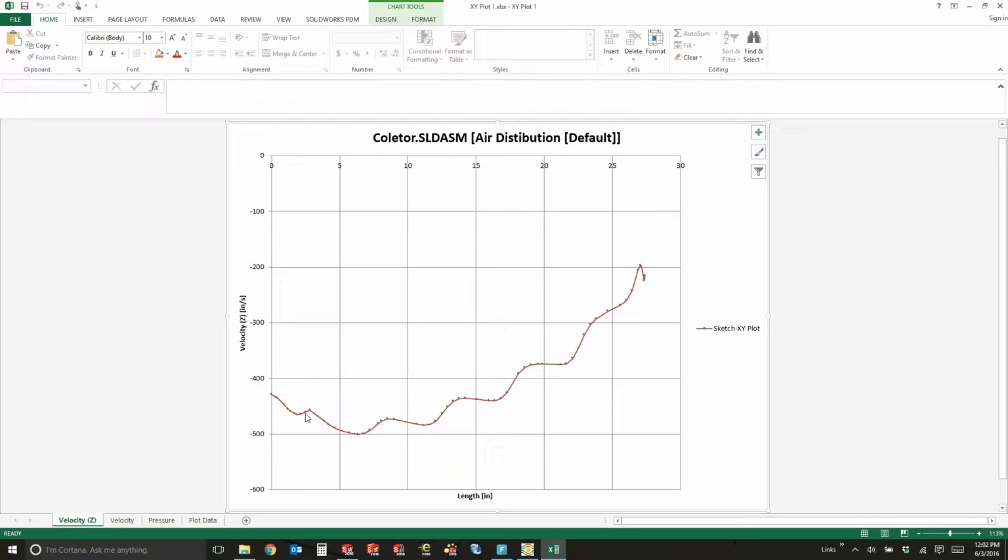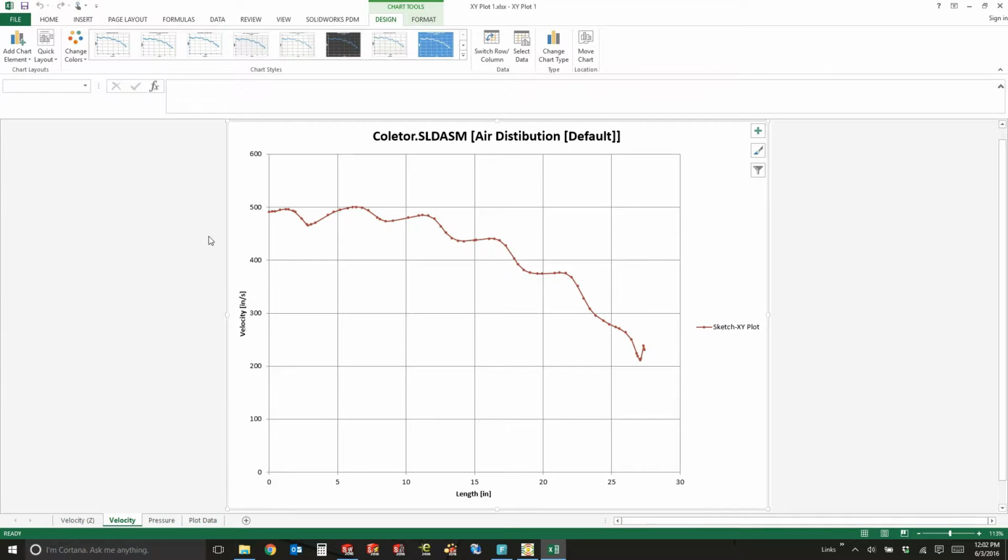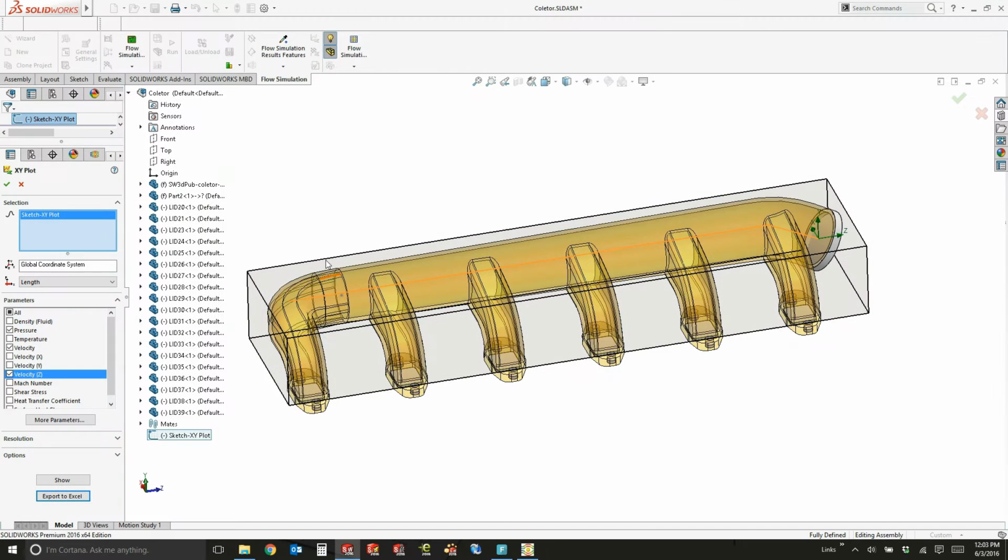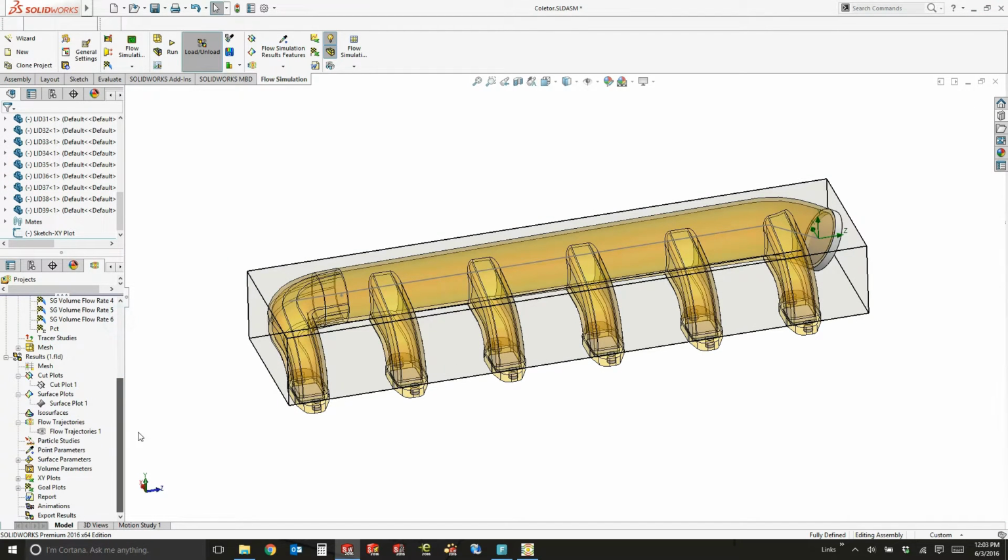And you can actually see as the length goes along, the velocity starts to decrease. It starts to get closer to zero, and you can see little bumps where each one of those outlets is causing an impact in the flow parameters. So these variables and these values would make it very easy for me to compare this one design to the next and to really understand a percentage of change, or perhaps an effect on the flow rate of each individual outlet or point. Just because I didn't ask for all the values that I might be interested in, it doesn't mean I can't go and get those values and then generate all that data.